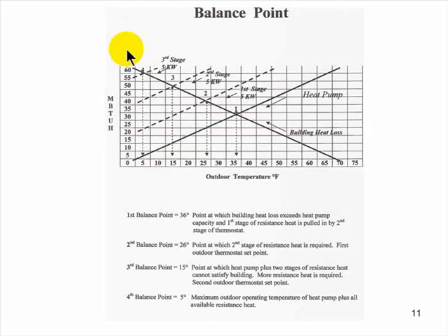And I can actually do this once I've done the heat loss and heat gain in a building. I know what this line is, and I've chosen a heat pump. Because the manufacturer's data will give you heating values at two points, 47 degrees and 17 degrees. That's the two points you put in a graph. Draw the straight line.